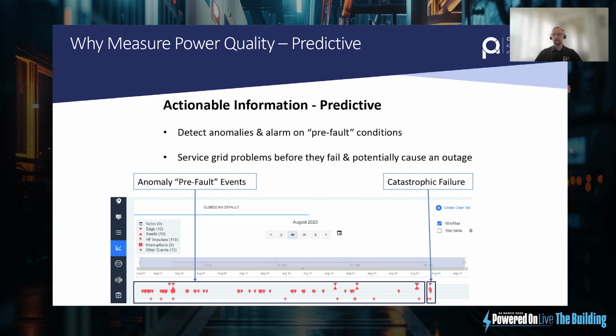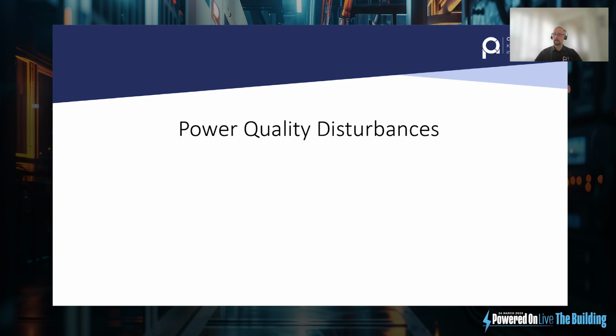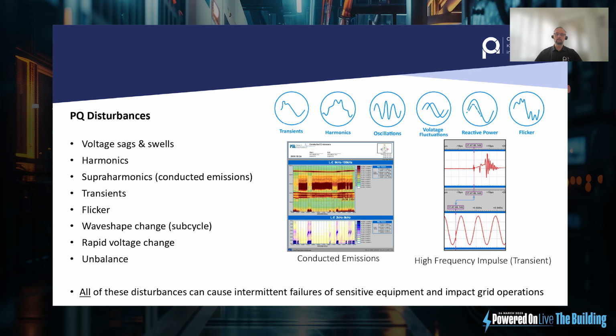It could be a cable breaking down. In terms of EV chargers, maybe one of the vehicles that's plugged in has got a bad battery or is not charging right, and then you start to see that that caused the problem in the charger because now the charger's not operating properly. You could trend that with the recording of the information that leads to you understanding that you might have a catastrophic failure, and you could predict that maybe service or investigation needs to happen. So quite powerful stuff, really, rather than being reactive, being proactive.